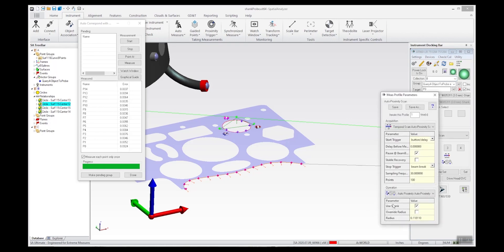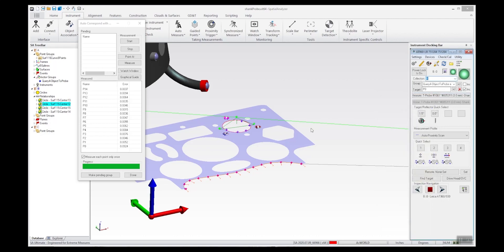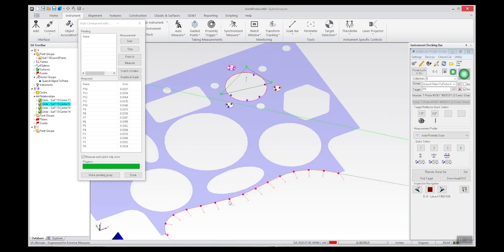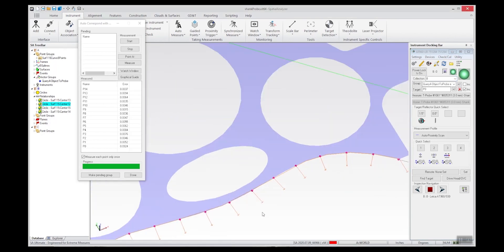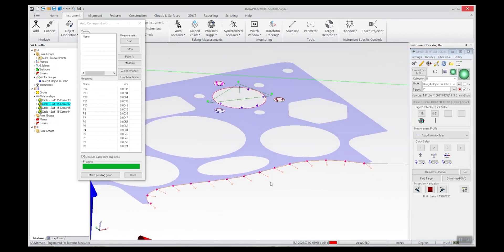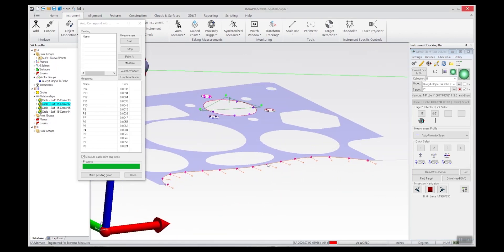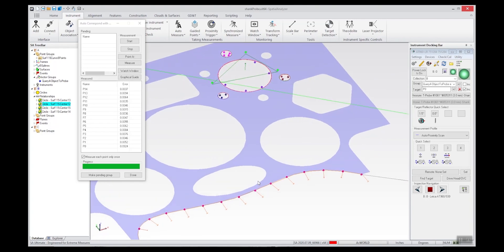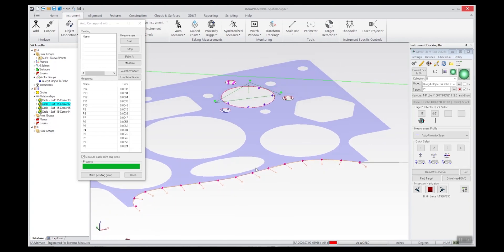You will be looking to use the tip of the probe, which is far below the vector. Those are two little details I thought might be worth sharing. That's a couple of tricks on how to measure a sheet metal part with the T-probe and a calibrated shank.